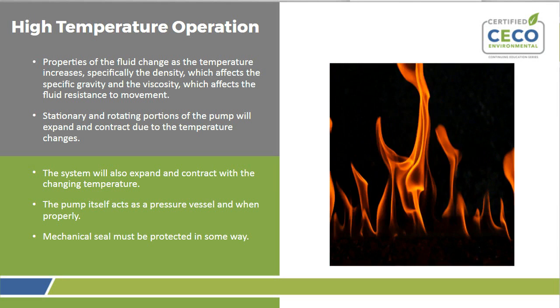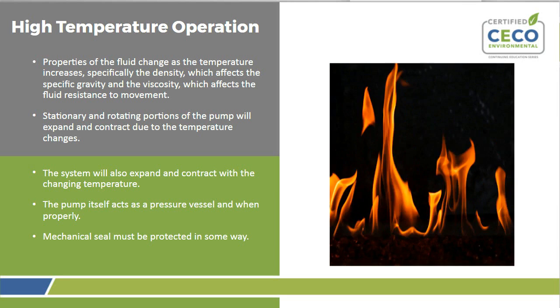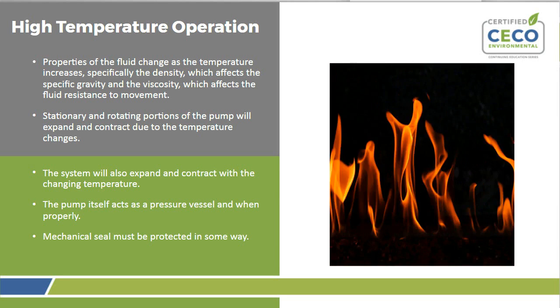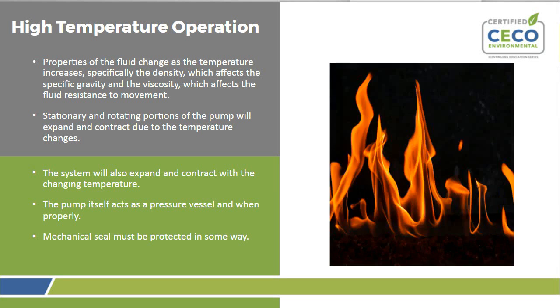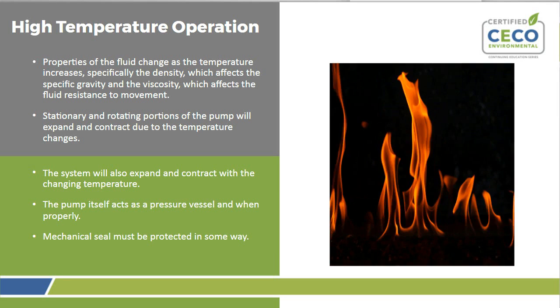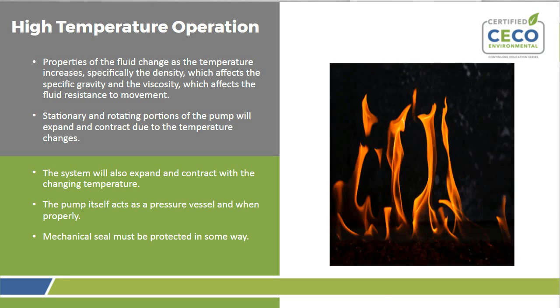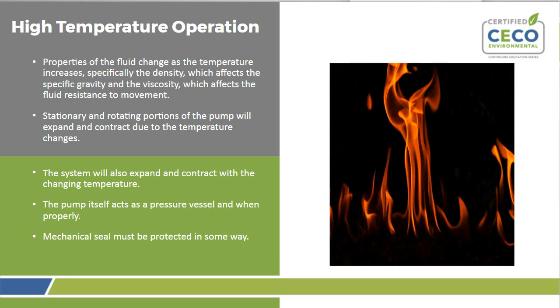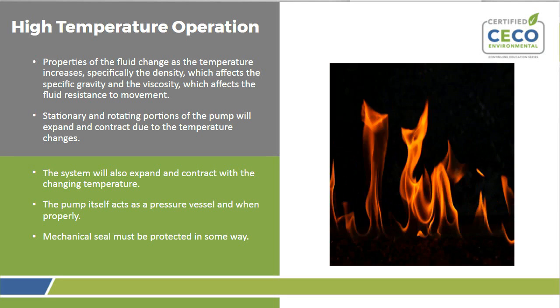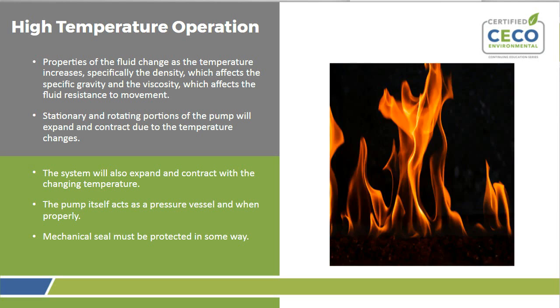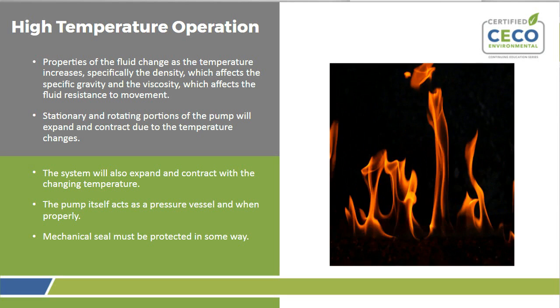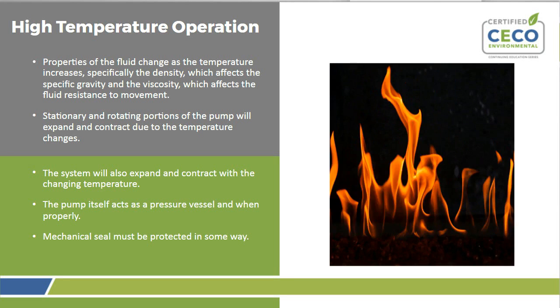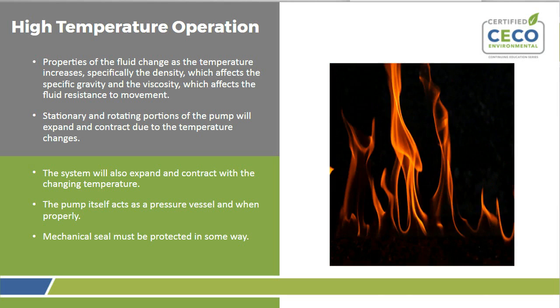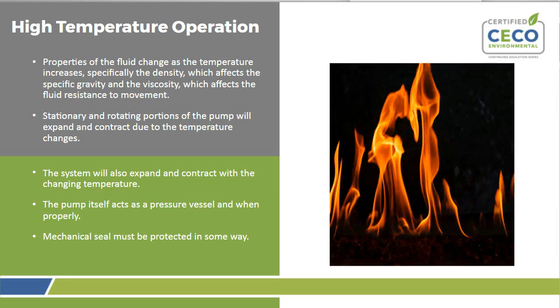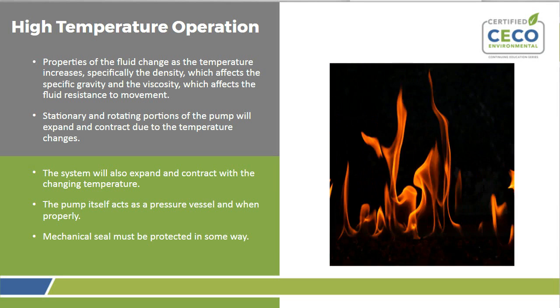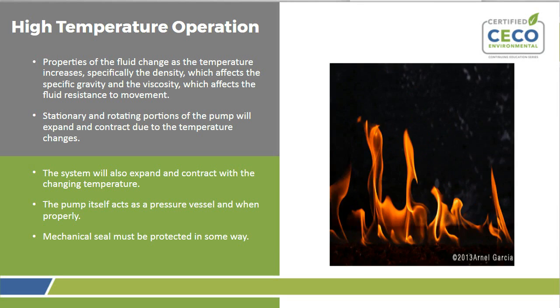The system itself, so what the pump is attached to, will also expand and contract with the changing temperatures. The pump itself acts as a pressure vessel when properly designed, and can handle the full range of the temperatures. The mechanical seal, however, is generally not designed to handle the full range of pressures and temperatures. So that's the last consideration. Now I'm gonna talk about each of these items individually, and how it affects the overall performance of the pump, and how it affects the design of the pump, and how we look at it and consider it in the application.